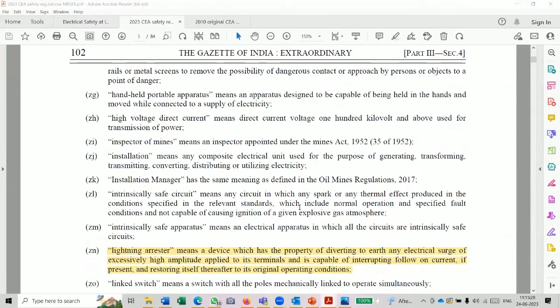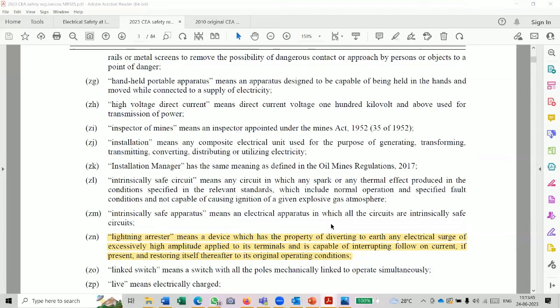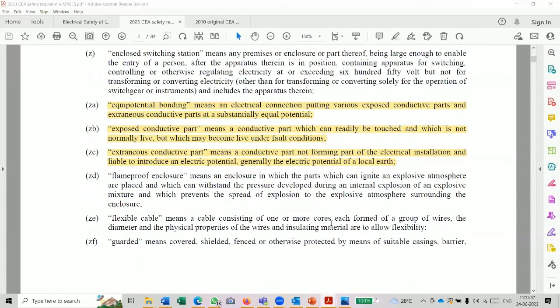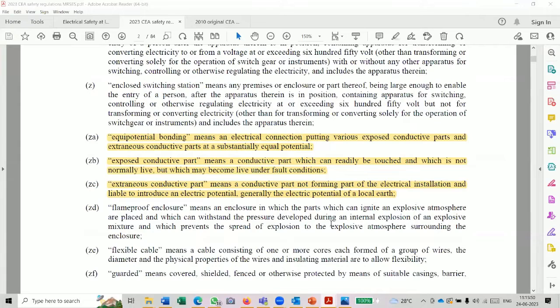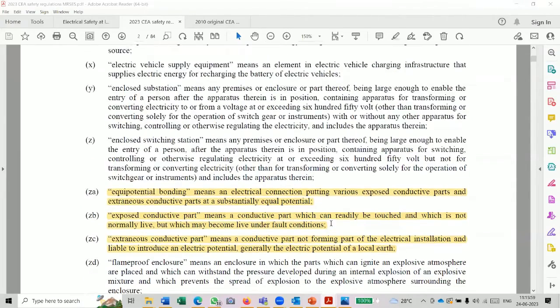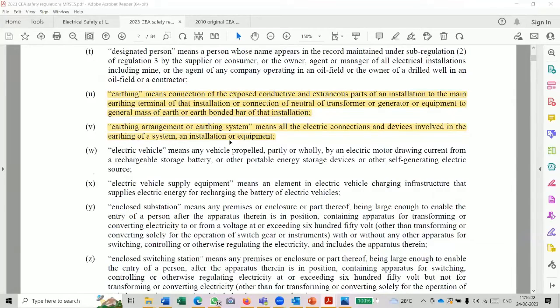Okay. Yeah. Sir, Mr. Gopal, sir. Yes, please. Hello. I think Amrit Ali is not convinced on this, so I can supplement some more. In the new regulation, most of the things have been resolved. Under the heading of earthing, up to not exceeding 650 volt, etc., what they mean is two separate and distinct connections with the earthing system. Previously, people misconstrued that there should be some earth electrode in the switchboard at one end and another earth electrode at the lift and something going on.